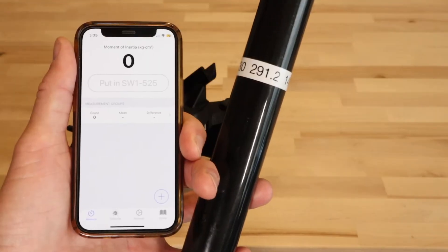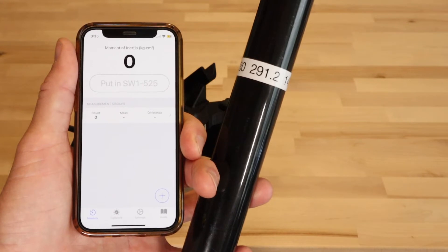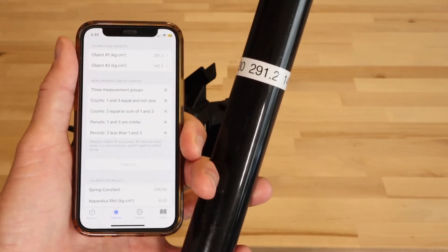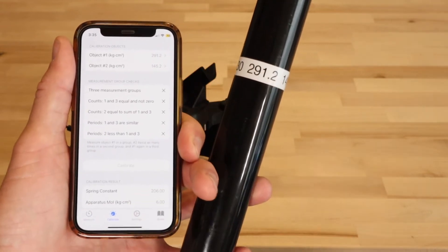In a prior step, when you scanned the NFC tag to add your device to the app, the calibration values were set to match those on the calibration rod label. You can see these values at the top of the calibrate tab.